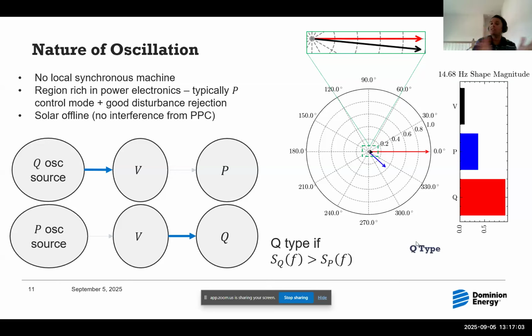You'll see the real power not even seeing that particular oscillation. It's a very good decoupling between P and Q in the way the controls are designed for our PV plants. So there is no reason that if a PV plant sees a voltage oscillation, its megawatt starts oscillating. We have never seen a case like that in our system. So even if something were to start as a volt-var oscillation, the challenge always is when will it turn into a megawatt oscillation also, and it all depends on frequency response of individual devices.